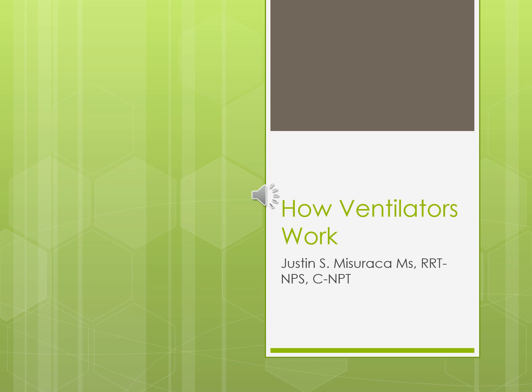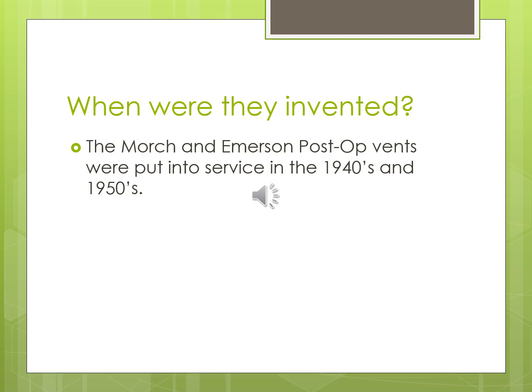Here are some cool facts about ventilators. Positive pressure ventilation has been around since the late 1940s and early 1950s. When you think of the technology back then, it's pretty impressive — the Emerson post-op vent and the Morch vent, which was a single-limb vent that could go underneath the bed and manage a patient without taking up too much space. That vent didn't have any alarms or safety measures; it was pretty rudimentary but did the job.